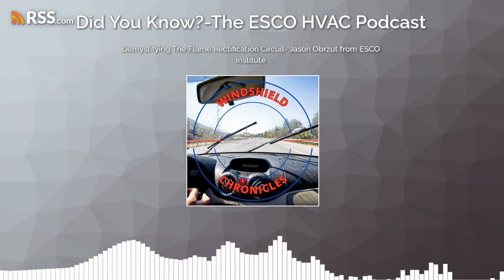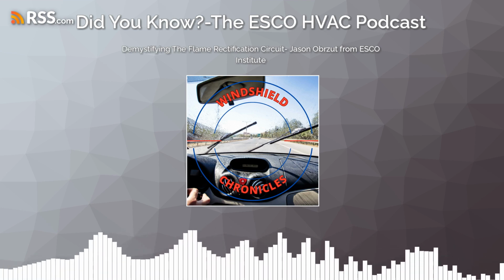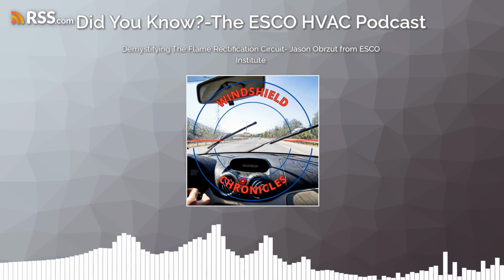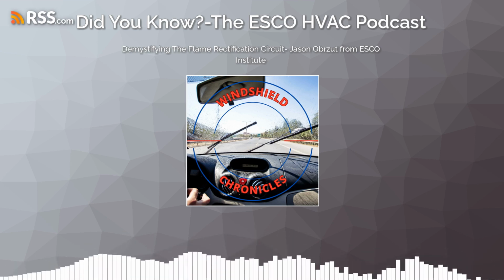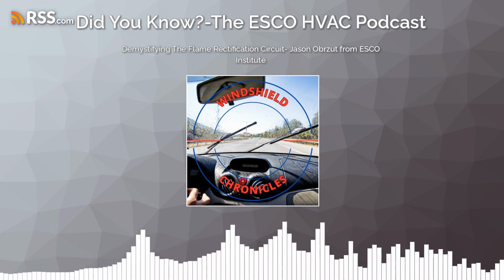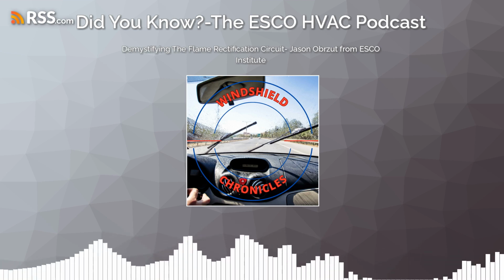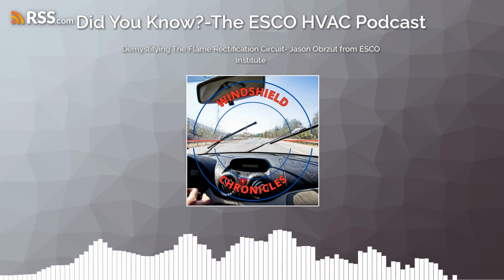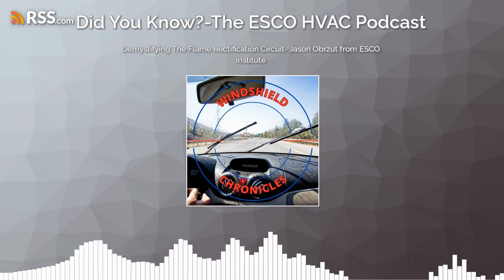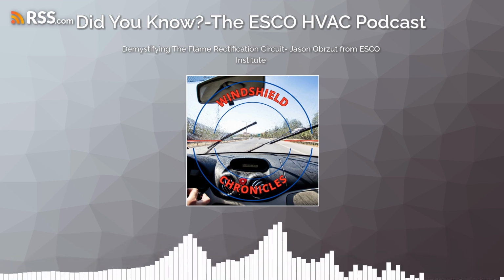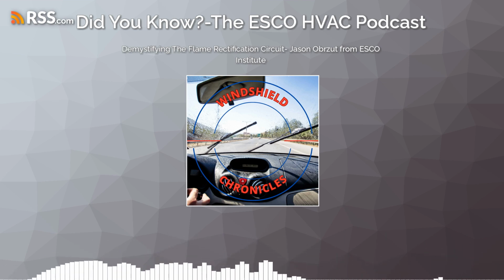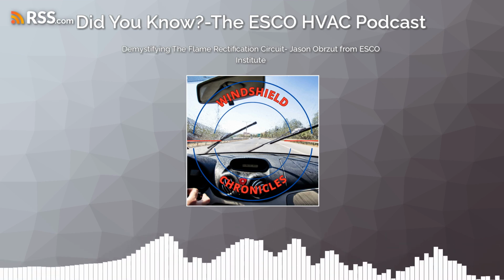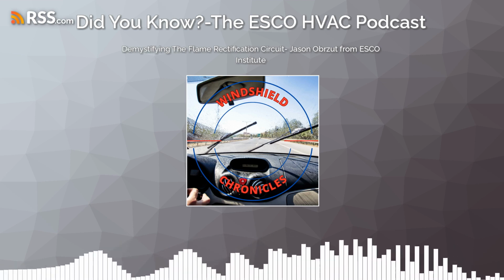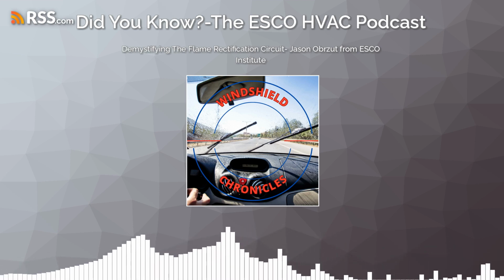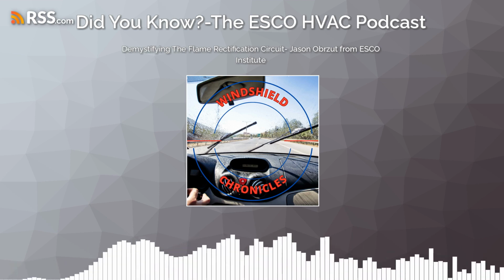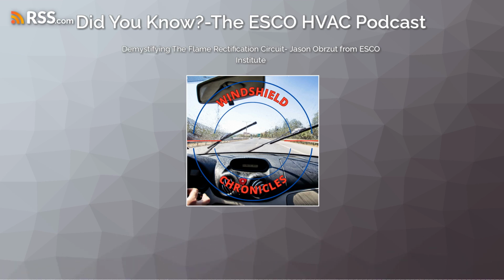So let's talk about this for a minute. If you've not had this explained, I'm going to very quickly demonstrate what we're going to do, and we're going to prove to you that it's actually electrical. If we are measuring the actual microamps passing through there, if we're measuring the load on that flame, what would we do? If we're measuring any kind of a load, we're going to put our meter in series with our load. So we're going to disconnect the wire, like I said, it's typically orange. We're going to disconnect it and put our meter in series.